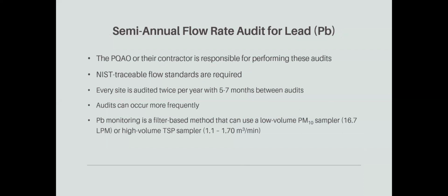Semi-annual flow rate audit for lead. I'm not sure how many of the networks you guys are involved with run for lead. There's pretty much no regulatory lead monitoring in Region 8. But for semi-annual flow rates, it follows a similar pattern as the PM 2.5 and PM 10. It's required at the PQAO level, NIST traceable flow standards, audits between 5 and 7 months apart. Of course, more frequently is recommended.